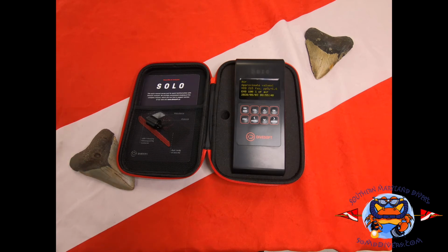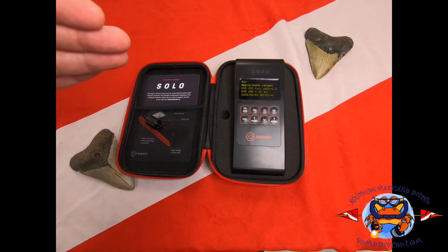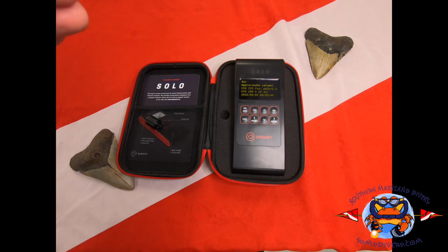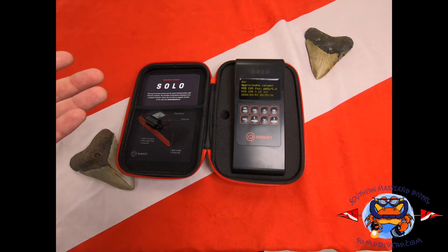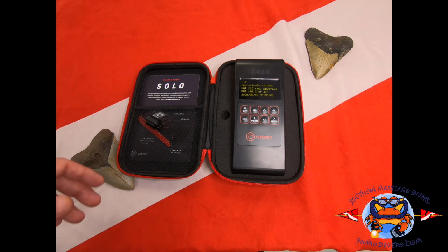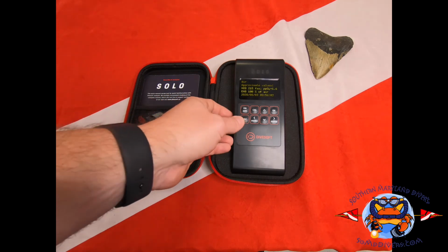And then the 3-point calibration would be used in the case of using it for helium, in which case the first point would be air, the second point would be oxygen, and the third point would be a known gas with no oxygen content in it at all. In the case of helium, we would use 100% helium, or even argon, something that has no oxygen in it at all. So it gives you a super detailed readout.